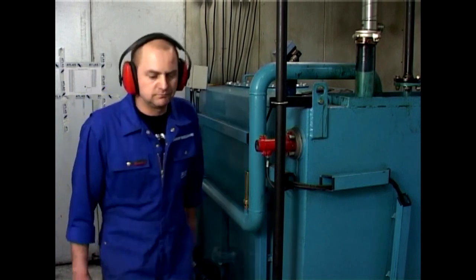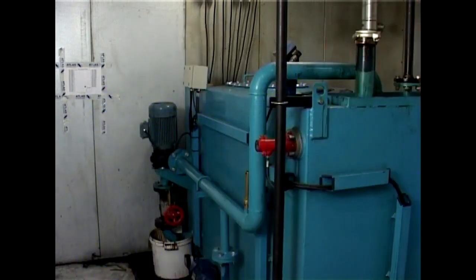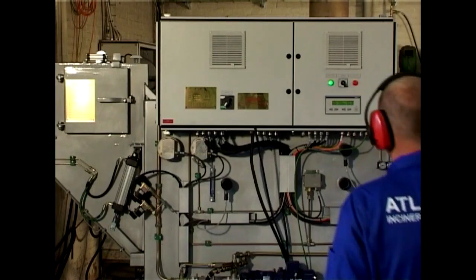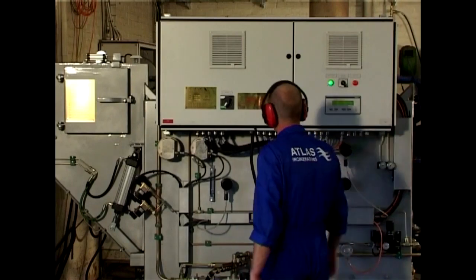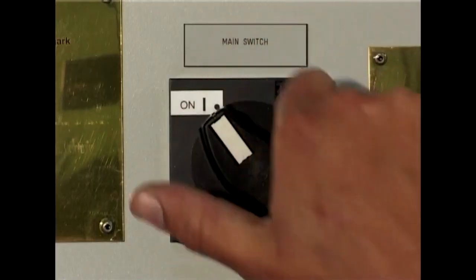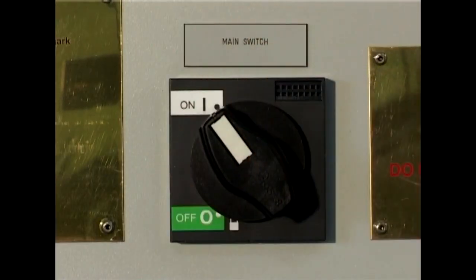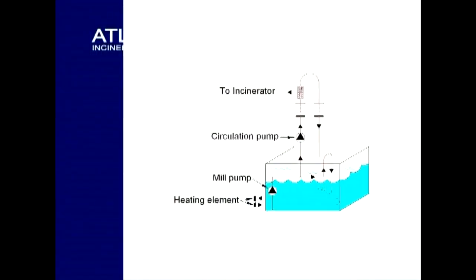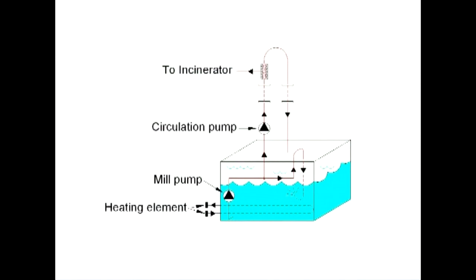Start the heating up of the sludge oil preparation tank 4 to 8 hours before you intend to start the incinerator up. To make the heating up as efficient as possible, you should switch the main switch to the on position on the incinerator control panel. This will make the mill pump and the sludge circulation pump start up, and sludge oil is circulated and heated up.